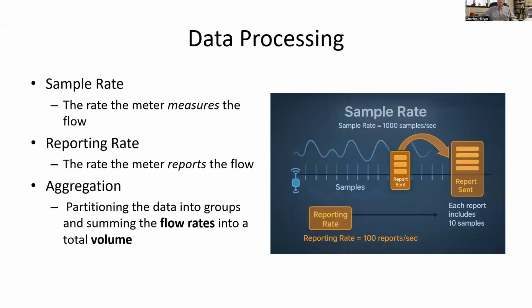Now, when this data gets up into the cloud, or when its calculations are being done in the meter itself or in the telemetry system, there's a lot of data processing that happens. And it's important to understand a couple of the key things that happen in data processing. First of those is the sample rate. The sample rate's pretty simple. It's the number of times that the meter measures the flow, or measures the thing related to flow, with respect to time. Now, the sample rate is oftentimes higher than the data that you actually see.